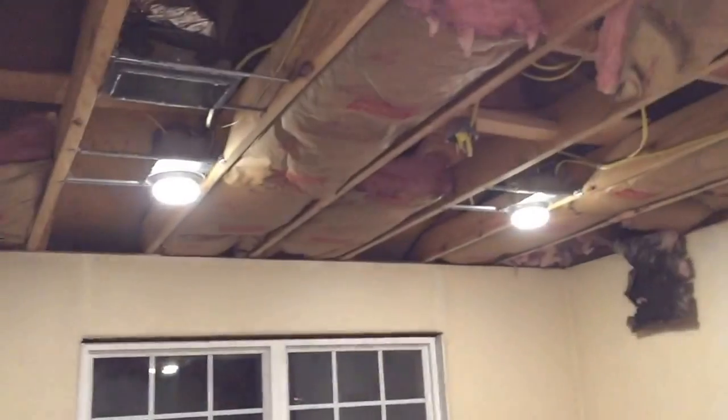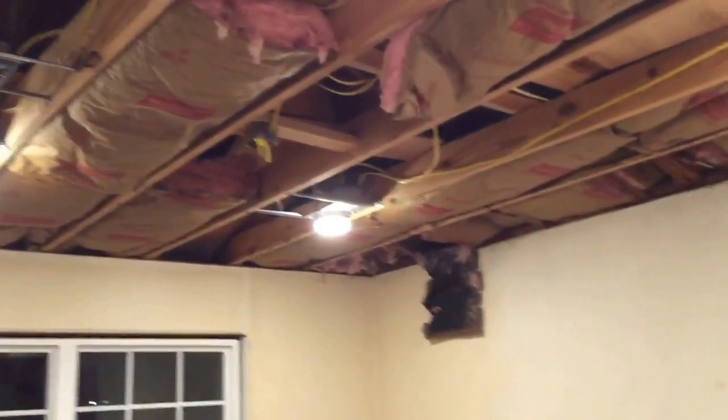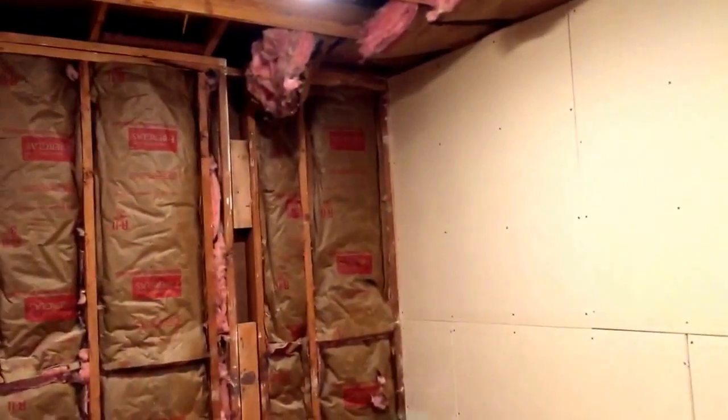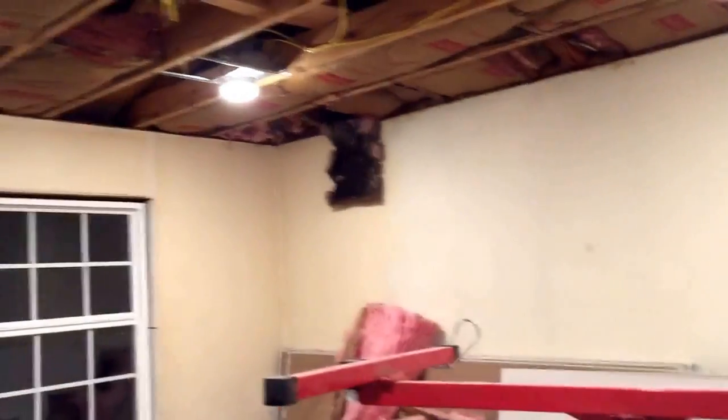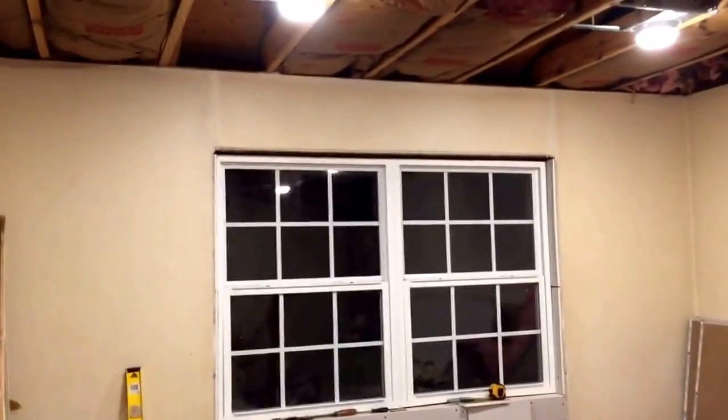So I'll tell you, I vote for 6 lights for this space. I was going to use a rule of thumb to make a choice on light selection for recessed lights. I'd go with the 1.5 watts per square foot, particularly if you're going to run a dimmer system. If we weren't running a dimmer system, maybe 4 or 5 would be better, and that's somewhere in between the 2 rules. But I'm loving it. I think six lights is the right choice for this room.